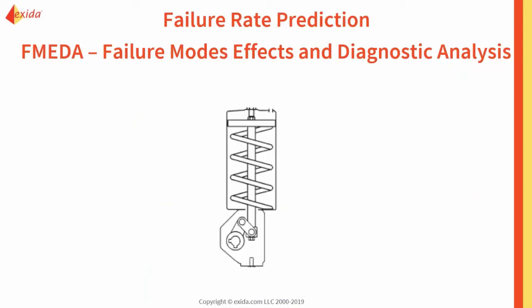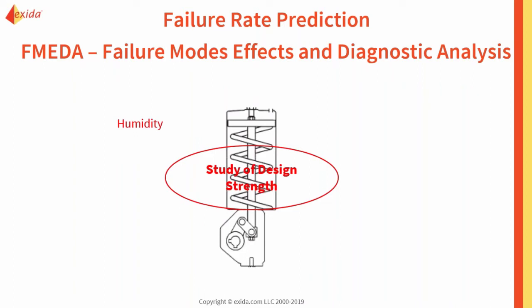So let's first look into the predictive techniques and the FMEDA. As I said, FMEDA stands for failure modes effect and diagnostic analysis. What we do is look at a device broken up into its bill of material in either an exploded view or a cutaway view, and we look at how it will react when we throw any sort of stress onto that design. So we're going to look at the strength of the design per the stresses this device could see or could come across. An FMEDA is a lot like an FMEA, but combined with the Military Handbook 217 stress methods, plus looking at diagnostic analysis, we can expand that and achieve component failure rates and failure modes along with diagnostic coverage and its effectiveness.